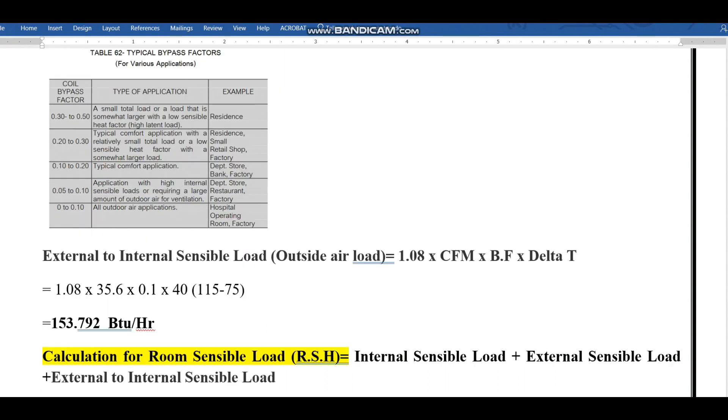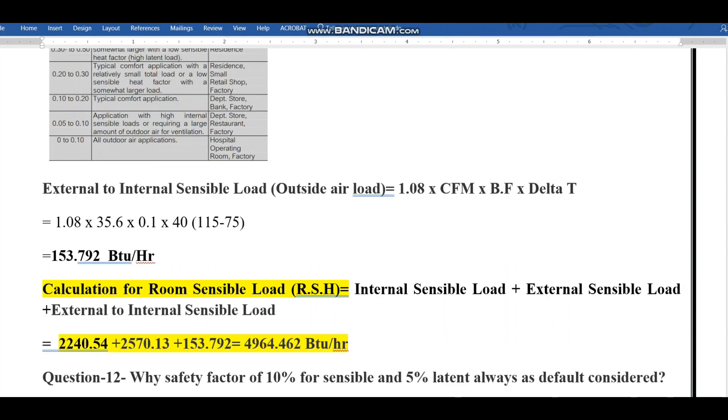Finally the answer is external to internal sensible load, outside air load equals 1.08 times CFM. We received from the number of persons using the actual reference table, that was 35.6 CFM. Bypass factor for the initial stage we consider 10 percent or 0.1. Delta T equals outside temperature minus indoor temperature, that is 115 minus 75, which is 40. Total load is 153.792 BTU per hour.